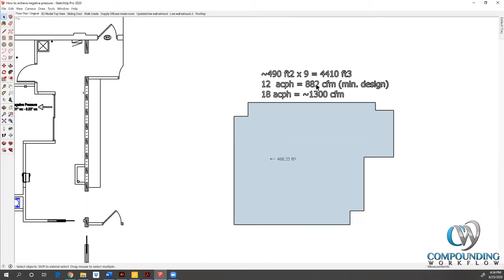We end up with a minimum design criteria of 882 CFM. That is going to be our actual supply. Typically, the certifier would measure or the test and balance company would measure at the ceiling grid the actual supply number and tell you the number of air changes.